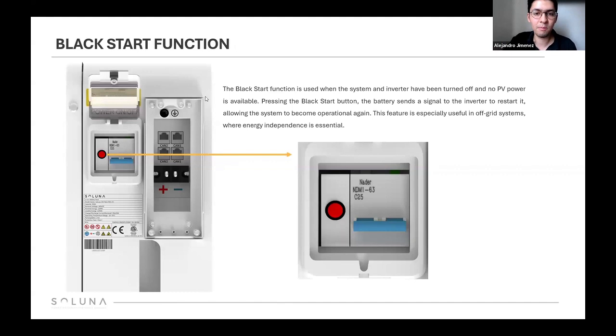Okay, black start function. Black start function is mostly for off-grid systems. For example, at night we have no solar PV, and if the inverter turns off, it's not possible to turn on the inverter again because we have no solar PV. So in this situation, you can press the black start button, and the battery will send a signal to the inverter to start. This is very usable in off-grid systems because in an emergency situation, you can start the inverter with the battery using the black start function. Another situation could be an on-grid system where there is a blackout of the grid and the inverter turns off; you can start the inverter with the black start function.